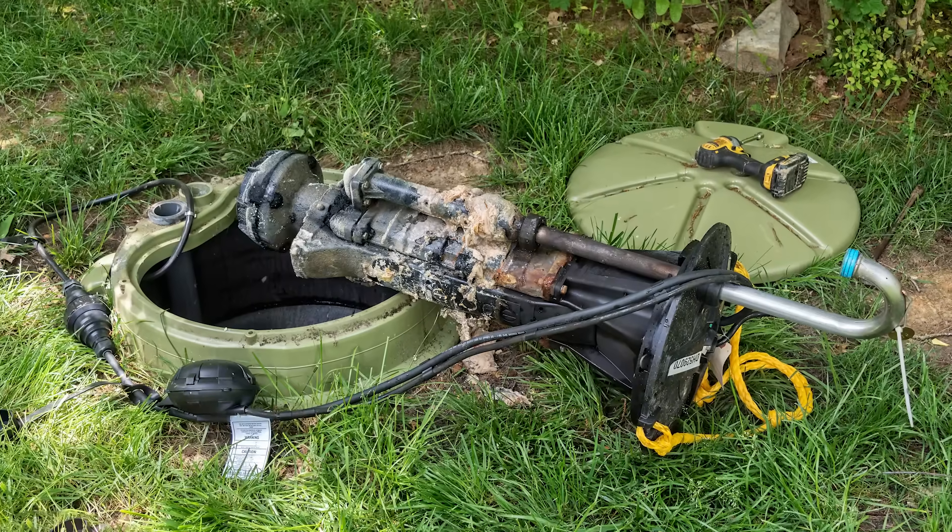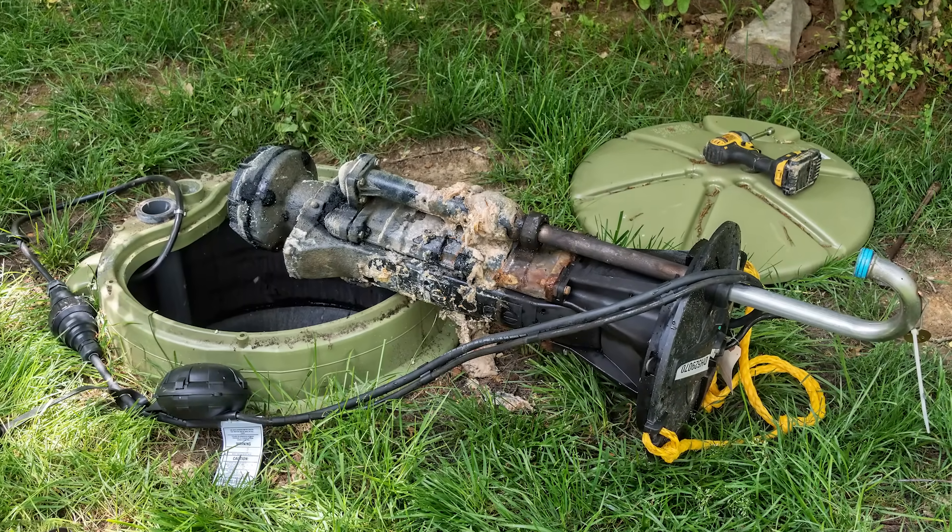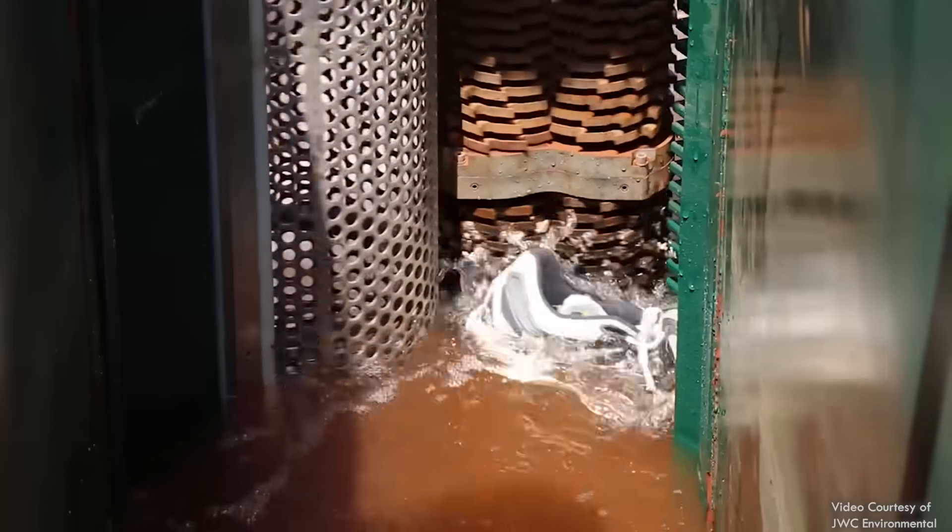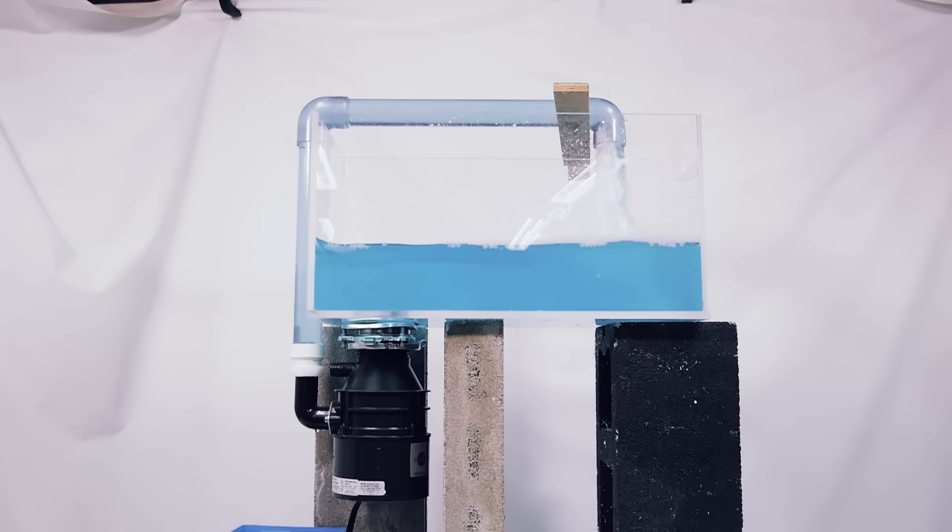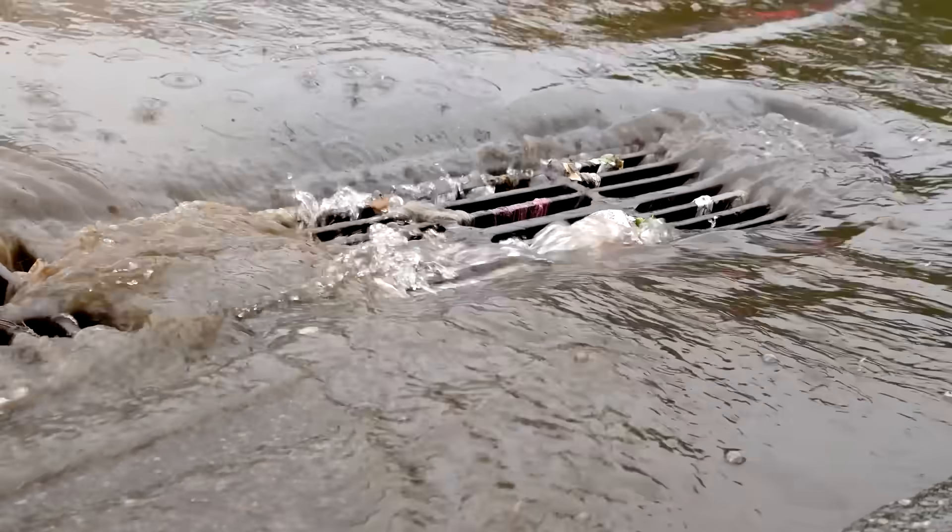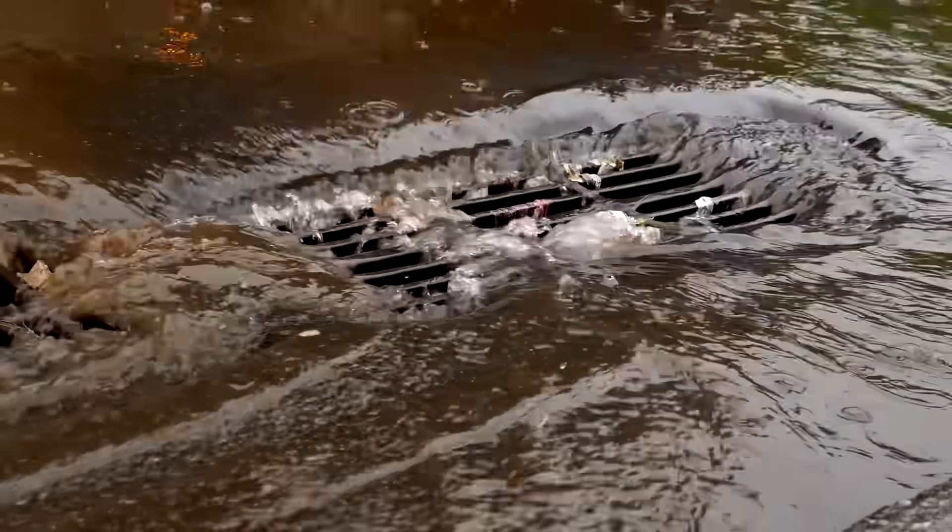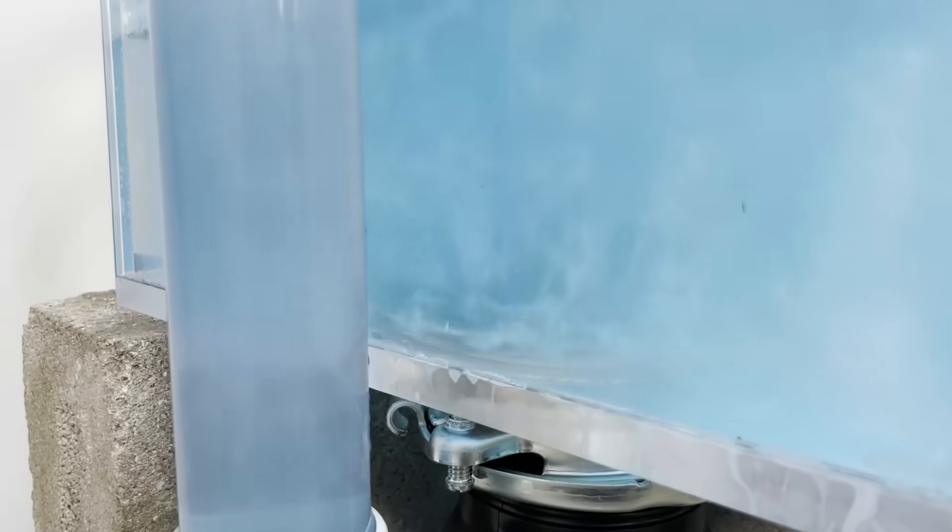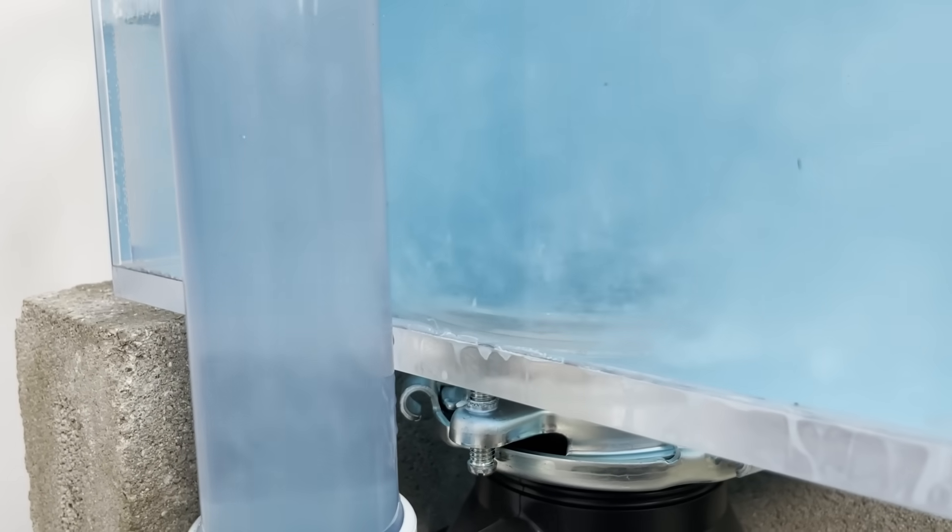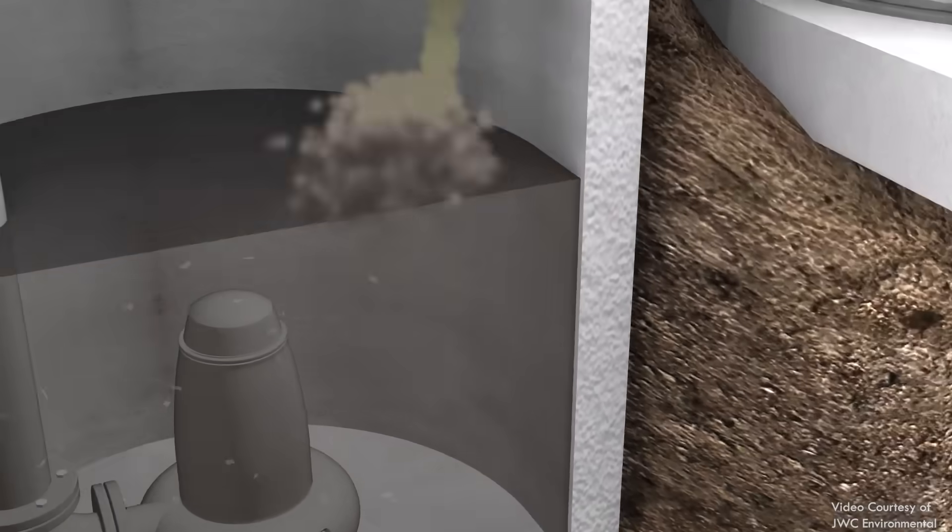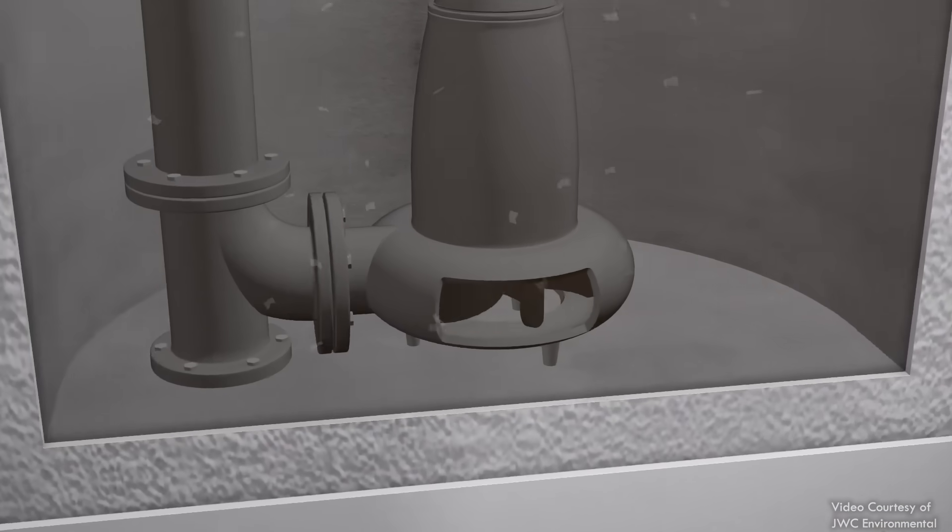Some lift stations feature grinding pumps that are remarkably similar to under-sink garbage disposals. Others use standalone grinders that simply chew up the solids before they reach the pumps. Grinders are often required at medical facilities and prisons where fibrous solids are more likely to find their way into the wastewater stream. Large grinders are also used where storm drains and sewers are combined because those systems see heavier debris loads from rainwater runoff. A grinder is another expensive piece of equipment to purchase and maintain at a lift station, but it can offer better reliability, fewer clogs, and thus decrease maintenance costs.